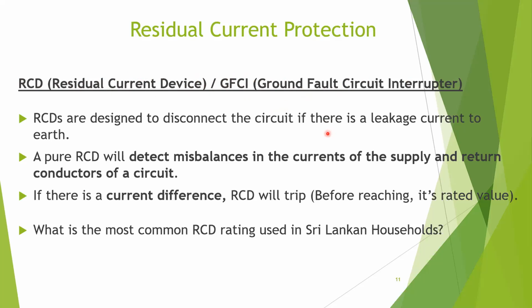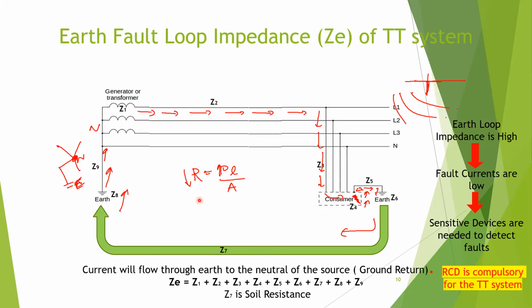RCDs are designed to detect leakage currents. In a system, if you provide some amount of current to the circuit, that same amount should come out through the neutral. It is simple Kirchhoff's current law. If you are providing current to a system, an equal current should come back through the neutral. If there is a leakage, there will be an imbalance between these two currents, and the RCD will find this imbalance and trip the circuit. I think you can understand. The usual current flow of this circuit will be that it comes through L1 and goes through the neutral. Can you understand?